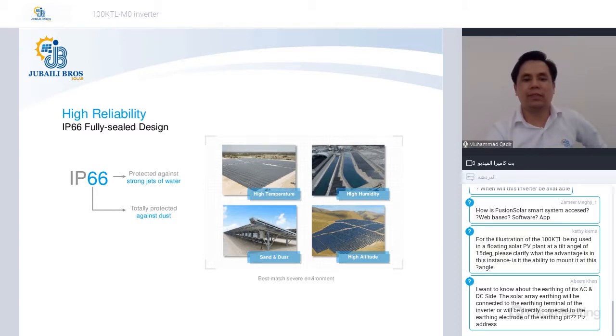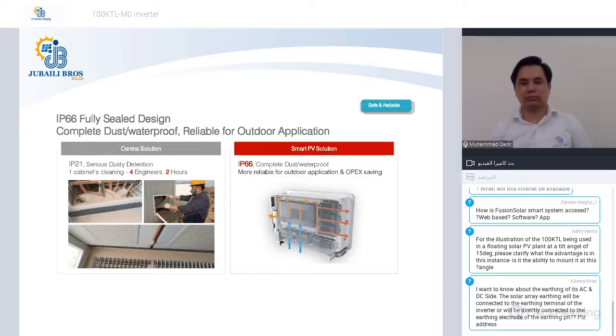Talking further about the reliability, Huawei has increased the IP rating from IP65 to IP66. These inverters can now withstand strong jets of water, and they can withstand high dust as well. Huawei inverters are IP66, as discussed. It is a fully sealed design, although this inverter has a cooling compartment at the backside, and the electronics compartment is fully sealed IP66. The cooling on the backside happens through three aluminum fans, which take the air from the bottom side and release it from the two sides of the inverter without going inside the electronics compartment, but cooling it from the outside.